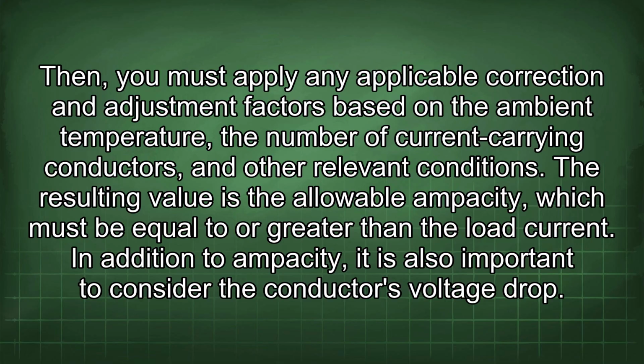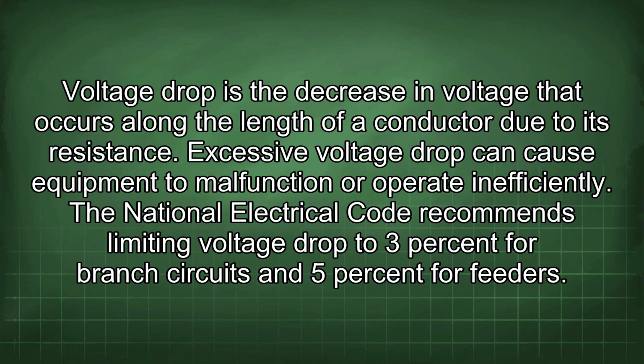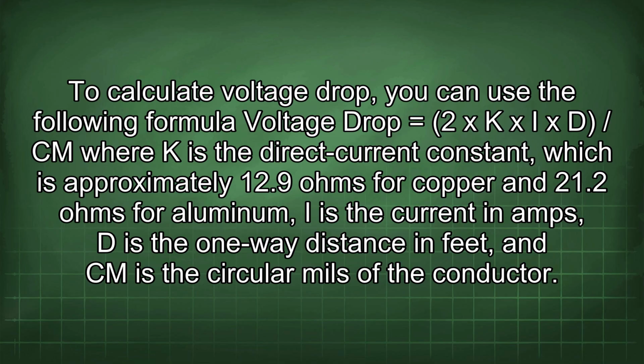In addition to ampacity, it is also important to consider the conductor's voltage drop. Voltage drop is the decrease in voltage that occurs along the length of a conductor due to its resistance. Excessive voltage drop can cause equipment to malfunction or operate inefficiently. The National Electrical Code recommends limiting voltage drop to 3% for branch circuits and 5% for feeders.